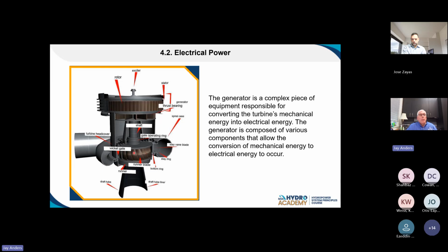As those wicket gates are opened up more and more, we have a shaft that connects the turbine up to the rotor. That's what we're showing right here, this rotating device. It's spinning in circles, just like the turbine below. And right on the very edge is where my stator winding is, which I'm showing here. It wraps completely around my rotor. So that's what we're going to talk about for the next few minutes, focusing on the rotor, the stator, the excitation system, and ultimately the governor, which controls the position of the gates.